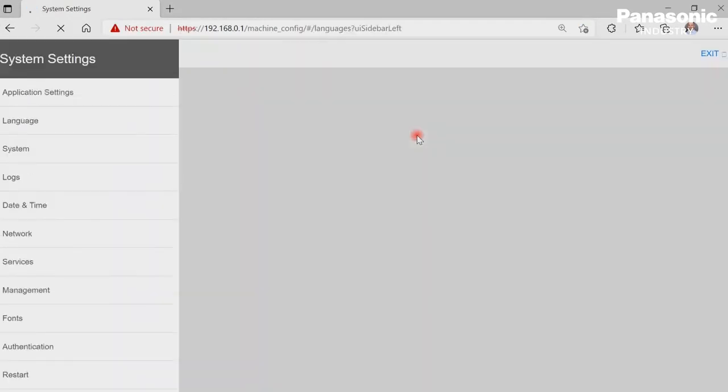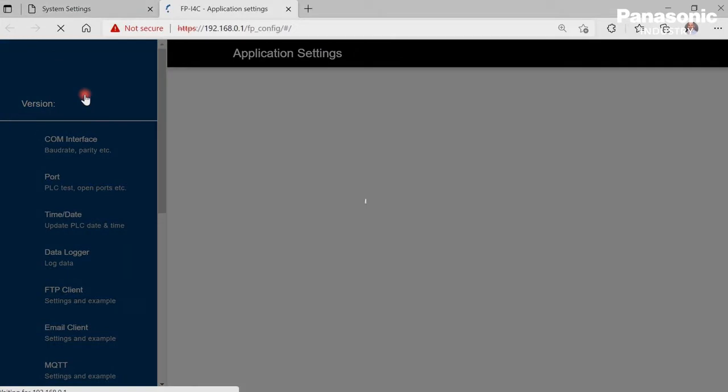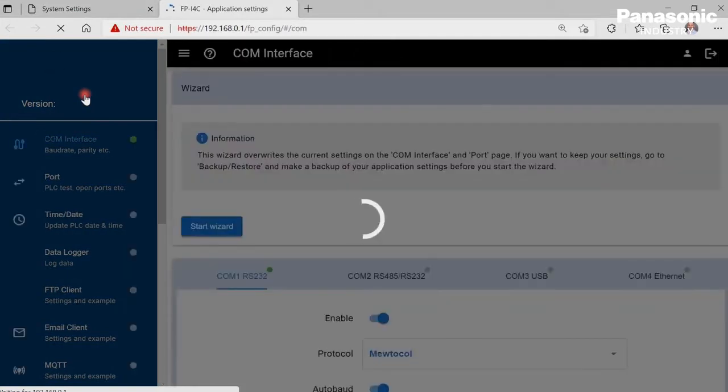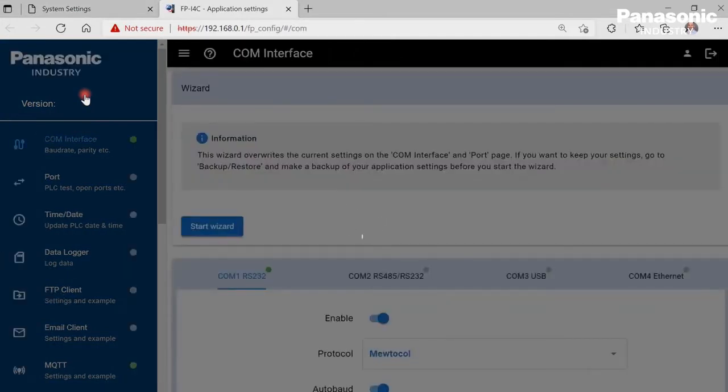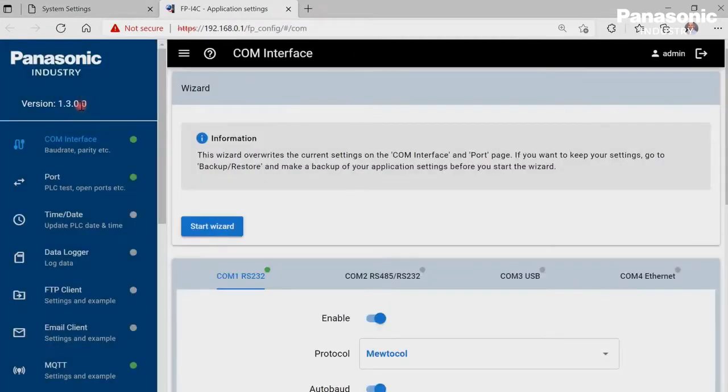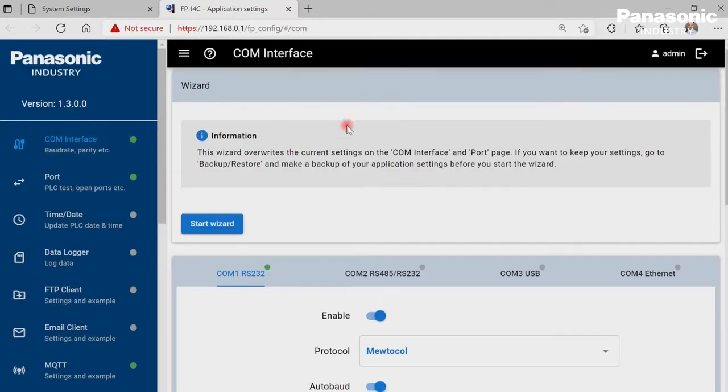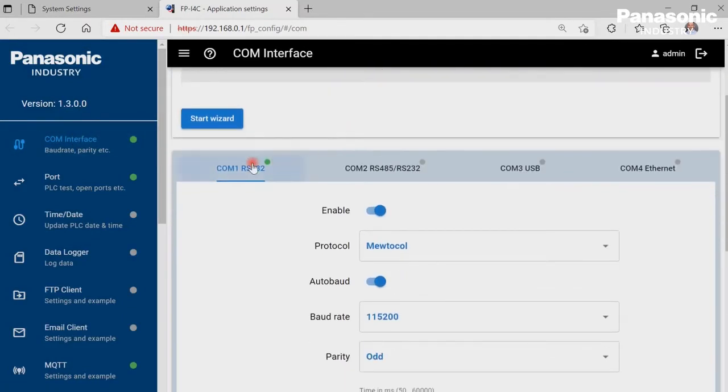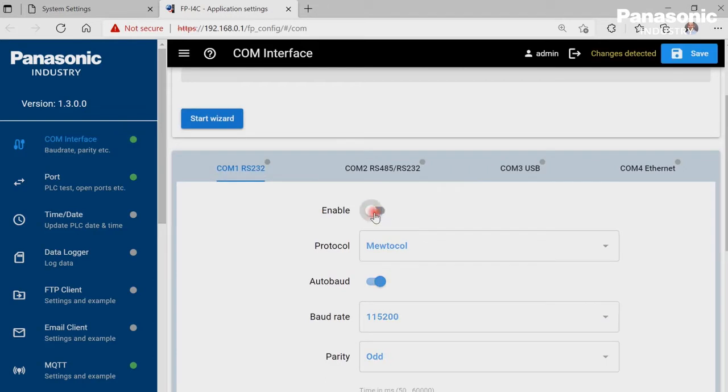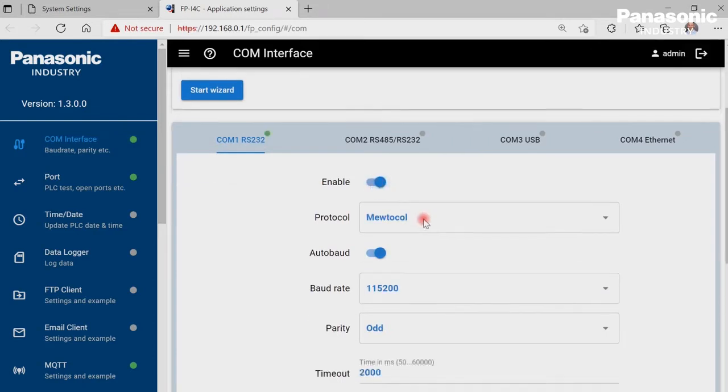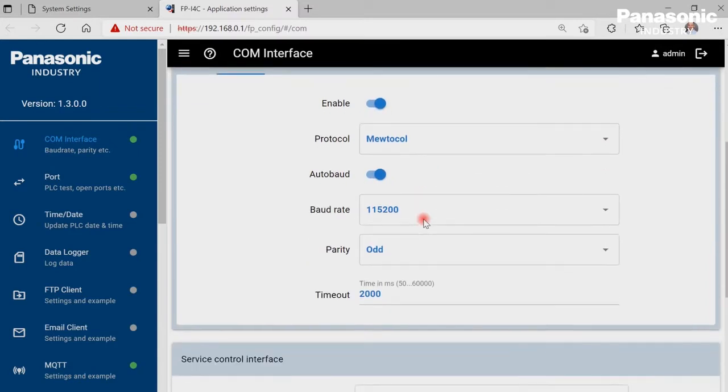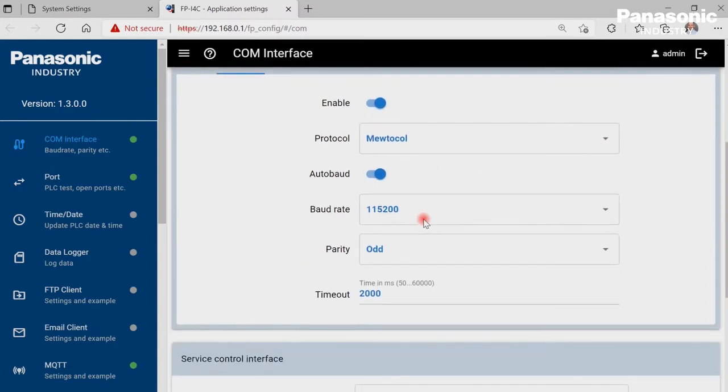Once we are connected, we can directly go to the COM interface page in the application settings area. We make sure that COM1 port of the FPI4C unit is enabled. We also make sure that the configuration settings for COM1 port are equal to the settings in the PLC for COM0 port.